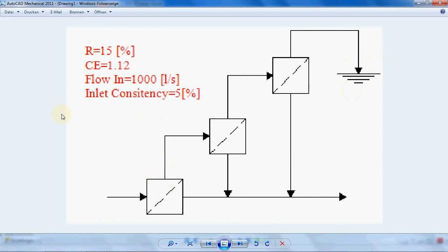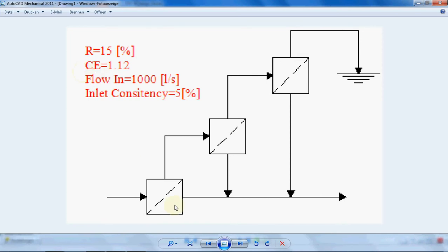In this design, first I have to say two properties of a screen are important: first is the reject rate shown by R and the second important parameter is the thickening factor. We assume that the reject rate for all these screens is 15% and the thickening factor is 1.12 as shown here.